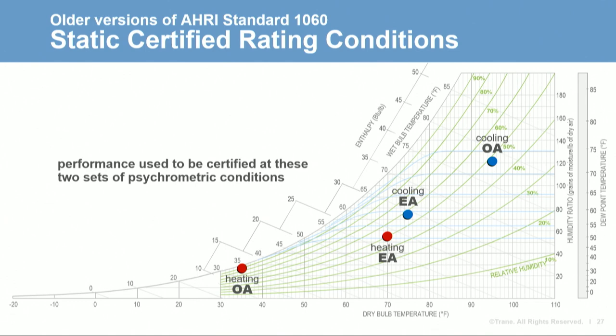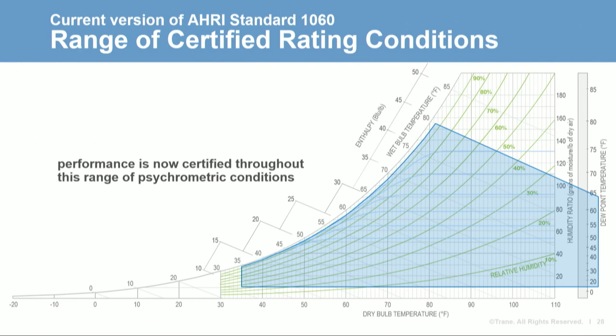In the past, AHRI 1060 defined two sets of air conditions for rating these devices — one for cooling and one for heating — similar to how we certify performance of a packaged rooftop unit. But in the latest version, this has changed to defining a range of conditions for certified performance, more like how we certify the performance of a chilled water or hot water coil. The energy recovery device is certified for any set of psychrometric conditions within the blue boundary. Note that AHRI only certifies down to 35 degrees Fahrenheit due to the difficulty of testing where frost might form, though these technologies are commonly used at colder conditions.